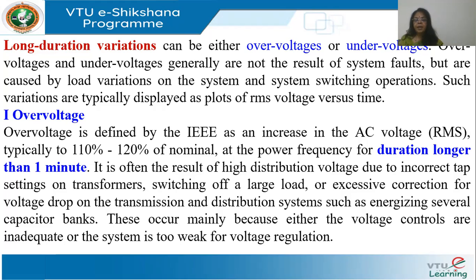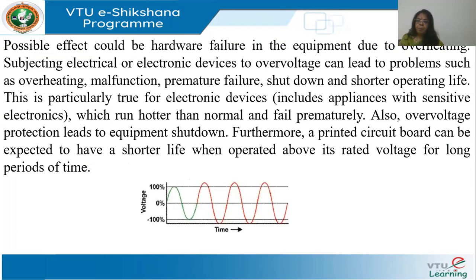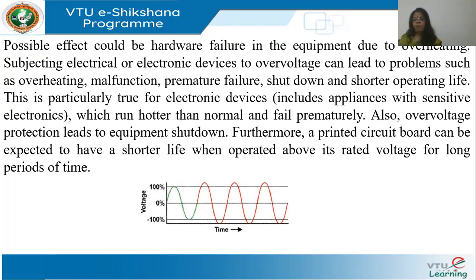These over voltages occur mainly because voltage controls are inadequate or the system is too weak for voltage regulation when many capacitors are energized. The effects include equipment failure due to overheating, permanent failure of electronics equipment, or process industry shutdowns. This reduces the life expectancy of equipment, especially true for electronic devices which run hotter at high voltage and fail prematurely.